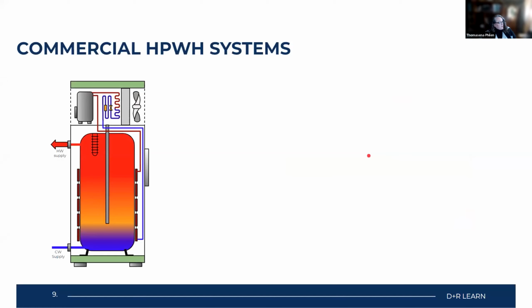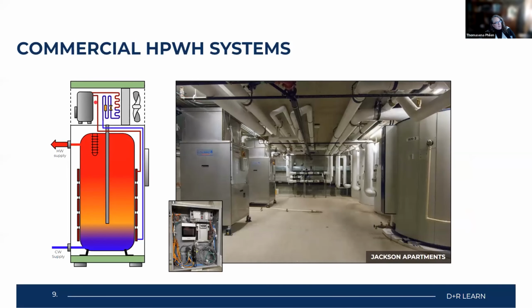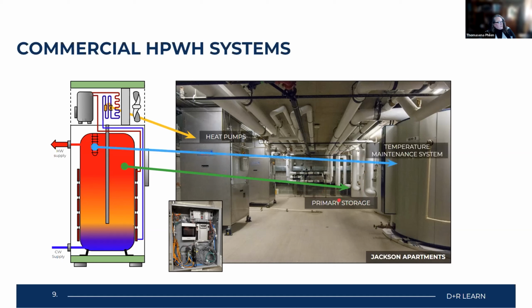Now, back to our little residential unit, we know that you've got the heat pump, typically, but not always, sitting on top. And then you've got your storage tank. You've got a resistive heating element here just to serve as a backup if needed. And then we've got our heat exchanger lining both sides of this storage tank. The same goes for a commercial heat pump water heating system, except for a matter of scale. So here is our heat pump. And then we have our primary water storage. So this supplies the hot water to the building. We also have our temperature maintenance system, and we'll get a little more into temperature maintenance and why that's important in a commercial setting, especially in multifamily. And then we have our controls.